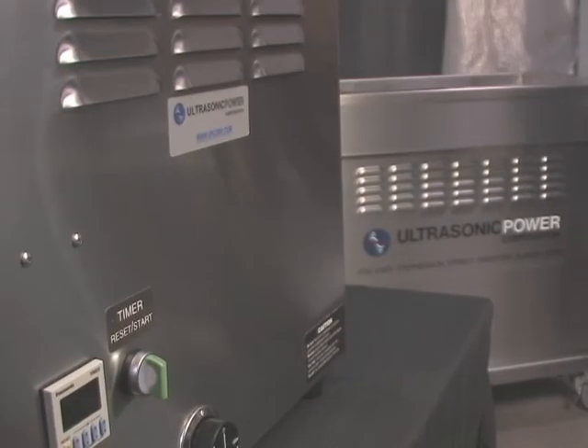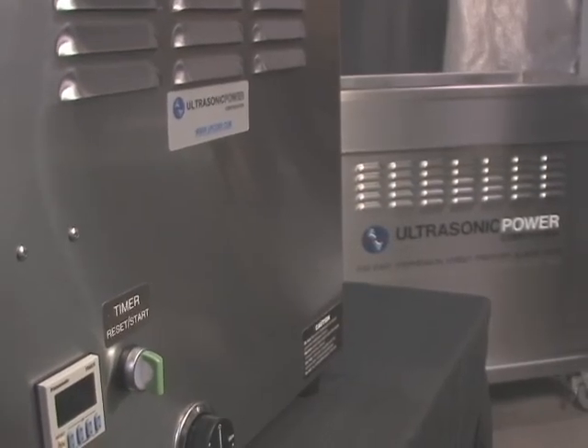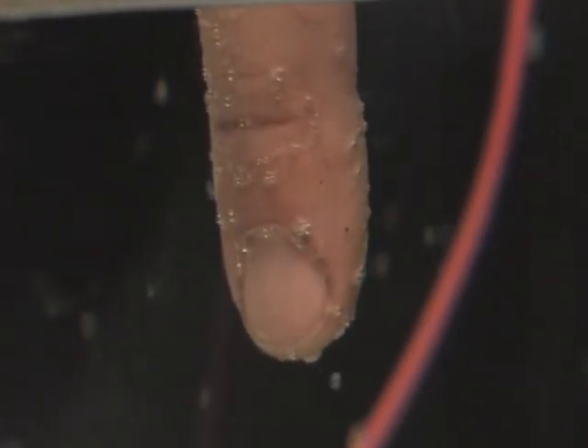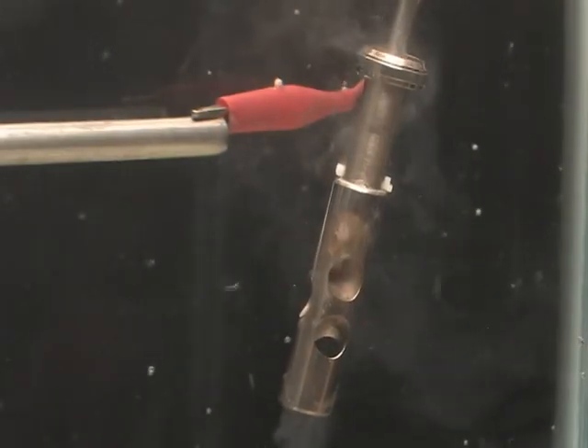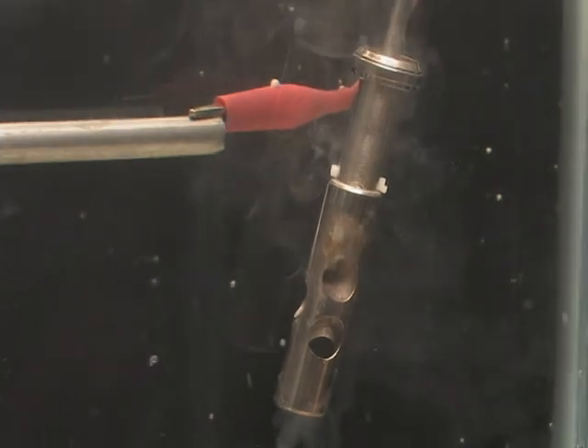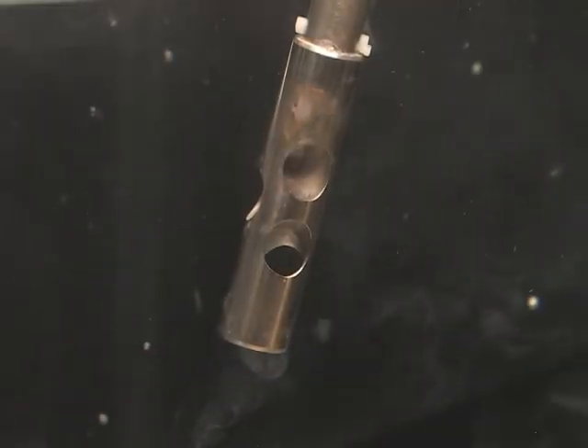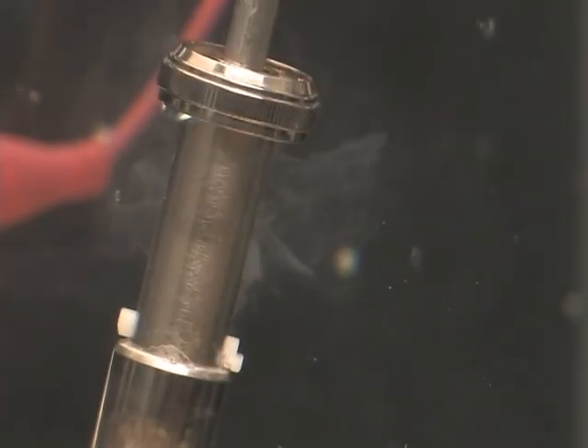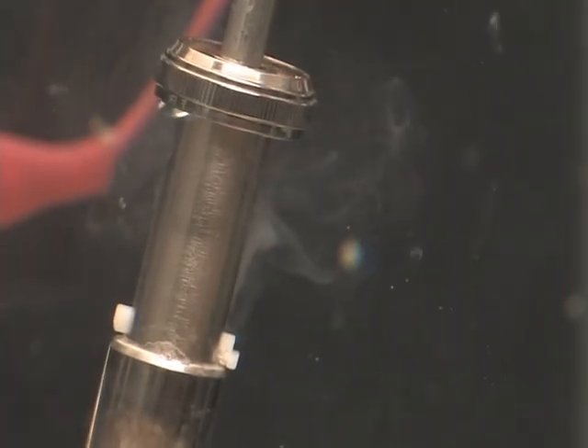Ultrasonic cleaning is based on a phenomenon called cavitation. When high-frequency sound waves are introduced into a body of liquid, they expand and contract, causing microscopic bubbles to appear. These bubbles, as they expand and contract, reach a certain threshold and implode. When this happens, it causes a 5,000 degree Celsius, 600 mile an hour jet stream that brushes up against the part's surface. It's technically a mechanical scrubbing action that's very thorough, yet very gentle on delicate parts.